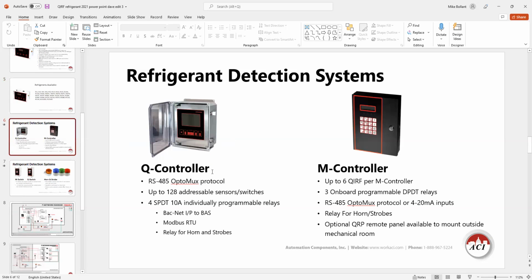Basically the same controllers, but to be honest with you, the only time you really would need a Q controller is if you need to interface back to your BAS with BACnet IP. If you don't need to do that, the M controller is a lot less expensive, as you'll see in a slide or two coming up, and it can handle up to 6 QIRFs, which would be a pretty large mechanical room if you get 6 of those covering 7,500 square feet each.